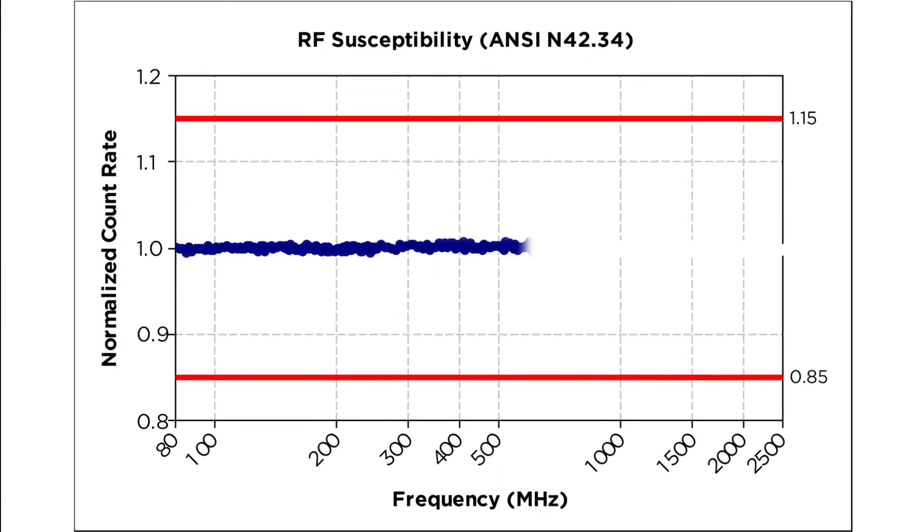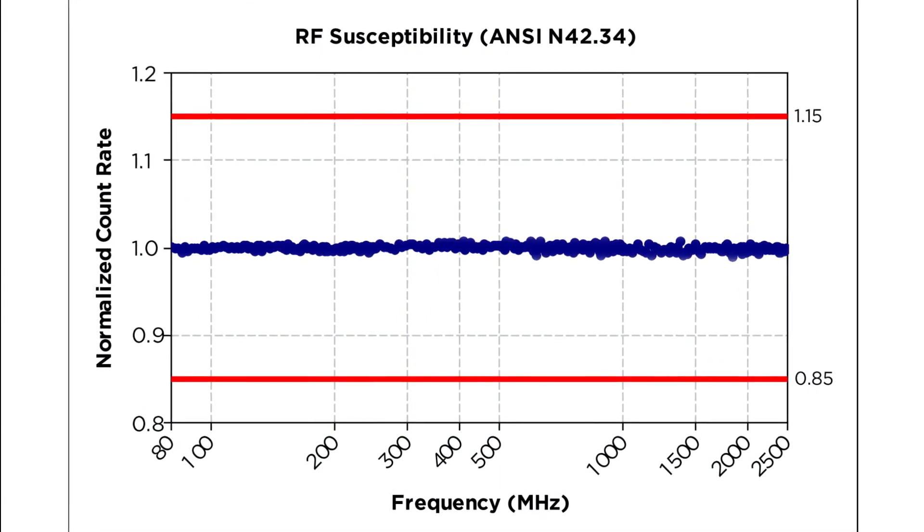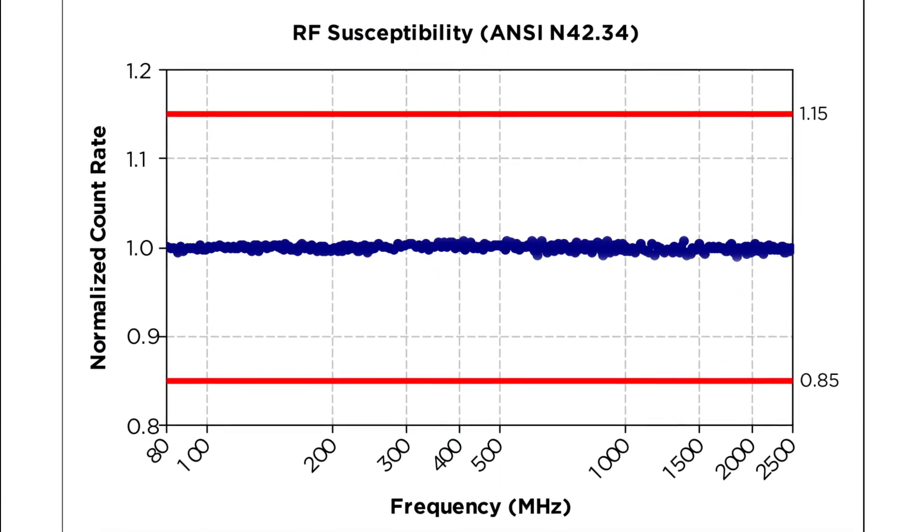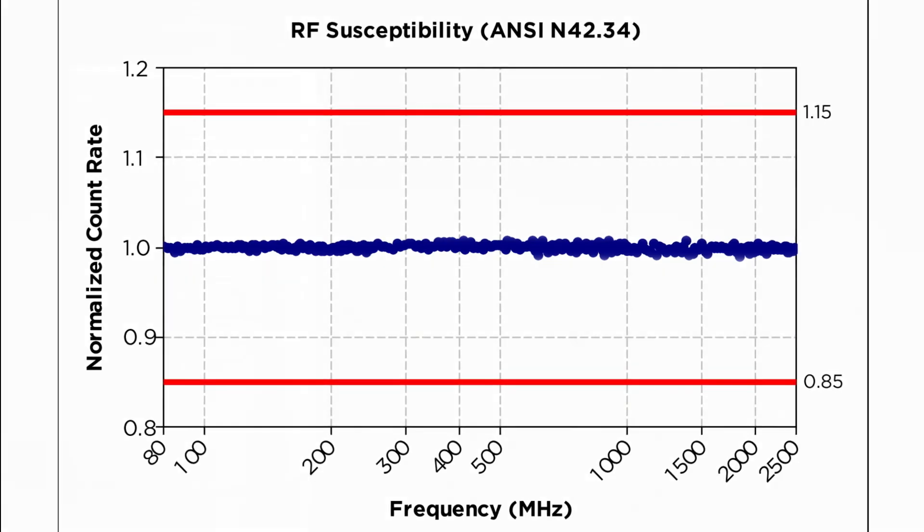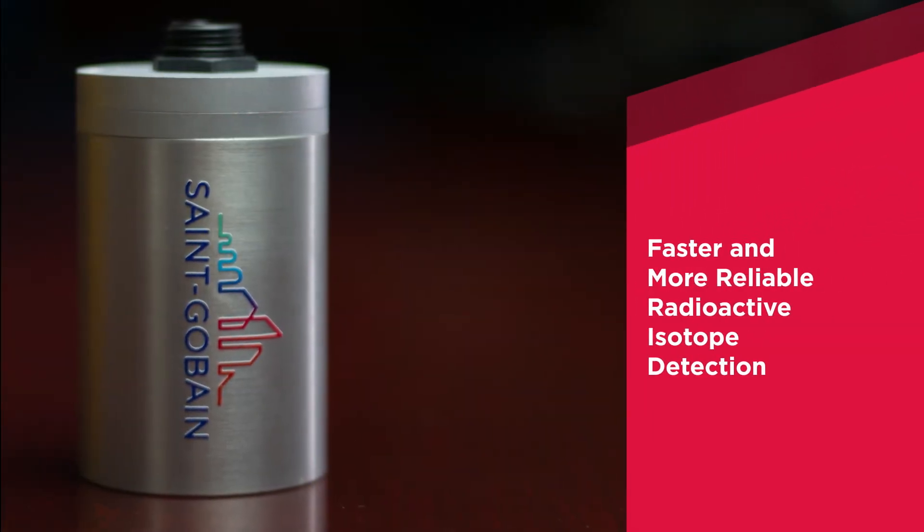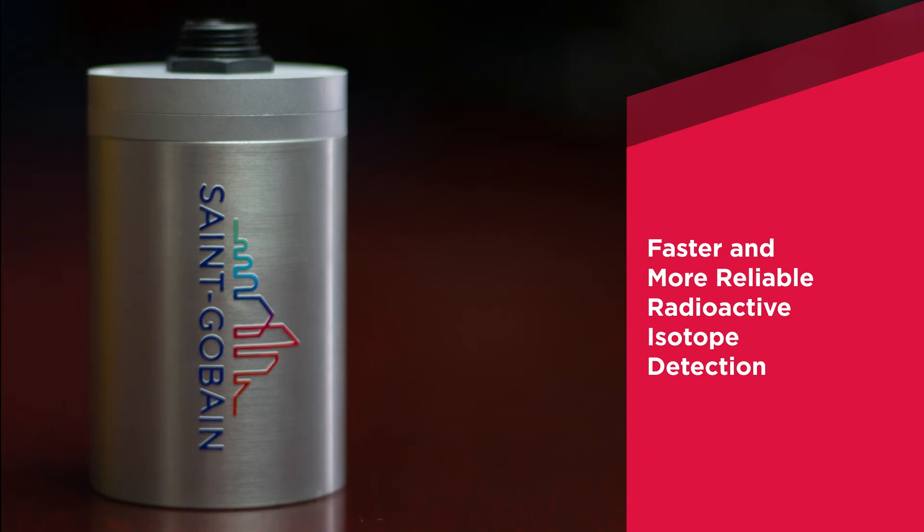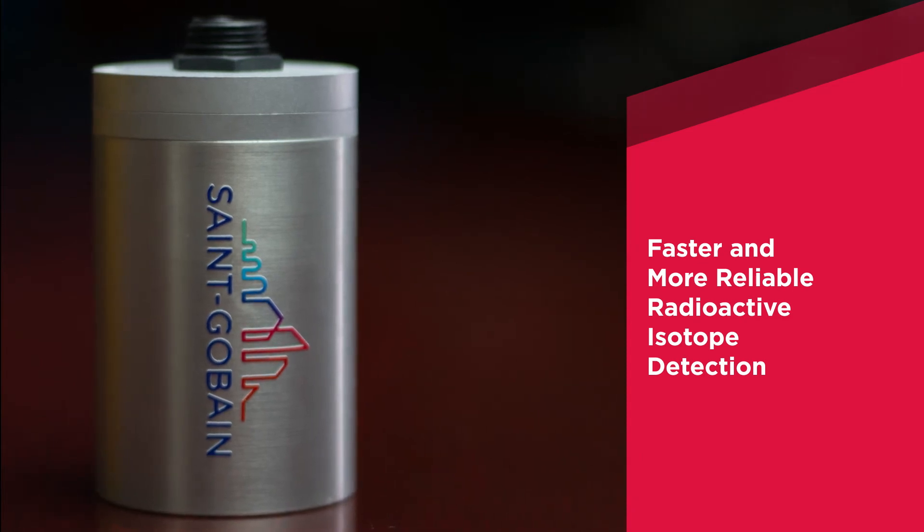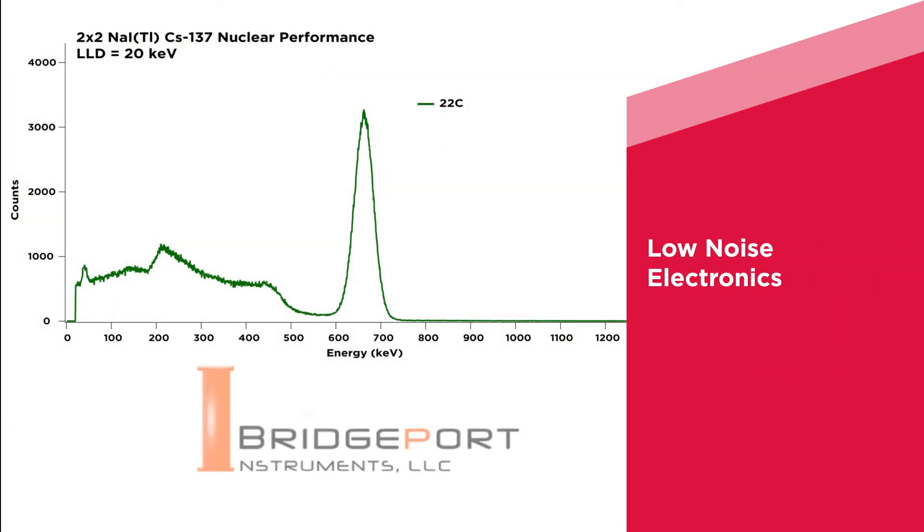We also understand that accurate detection is crucial, so our analog circuit dramatically reduces the impact of interference, giving you radioactive isotope identification that's faster and more reliable. To achieve this, we partnered with Bridgeport Instruments to develop low-noise electronics, such as the state-of-the-art multi-channel analyzer.